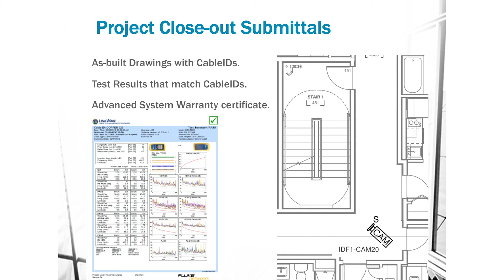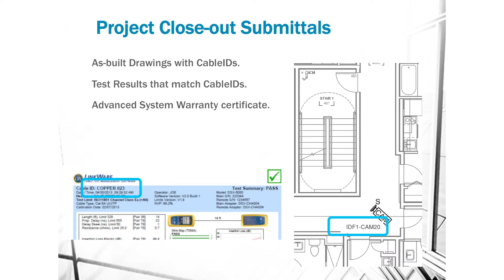The last bit I care about is project closeout submittals. These are things that tend to slip through the cracks. When I do my final punch and haven't seen these yet, I add them as a line item. You need to provide as-built drawings, test results, your advanced system warranty certificate, and - one of my pet peeves - the cable IDs on the plans need to match the cable IDs on the test results. Otherwise, how do I know this is truly for my project?